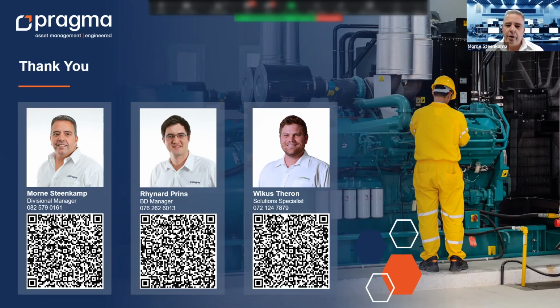For that reason, all of those things get monitored. As Wikus also mentioned, there are processes set up. So as soon as, for instance, a battery gets disconnected, the maintenance manager gets notified. If they don't respond and acknowledge the message, it gets escalated to a line manager typically. And if that person doesn't acknowledge it, it gets escalated to us, and then we start running around, especially if there's load shedding on its way.